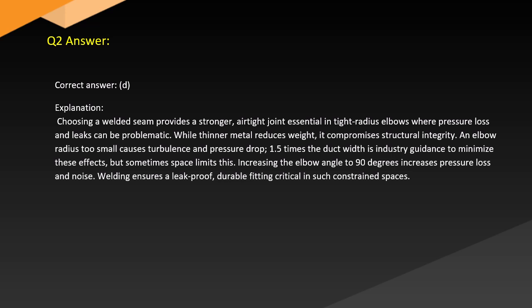It compromises structural integrity. An elbow radius too small causes turbulence and pressure drop. 1.5 times the duct width is industry guidance to minimize these effects, but sometimes space limits this. Increasing the elbow to 90 degrees increases pressure loss and noise. Welding ensures a leak-proof, durable fitting, critical in such constrained spaces.